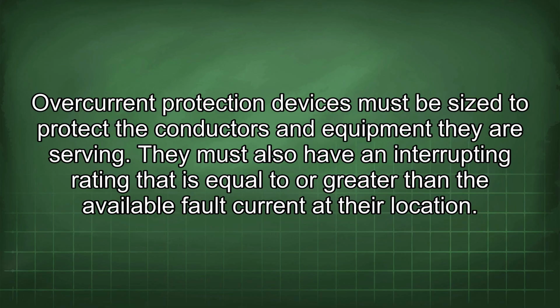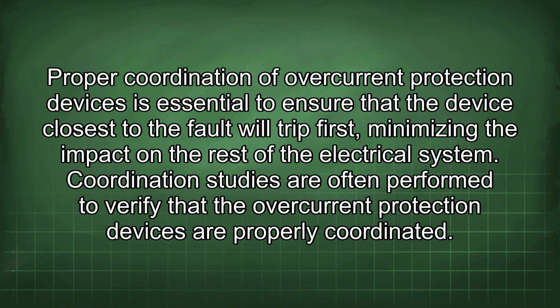Overcurrent protection devices must be sized to protect the conductors and equipment they are serving. They must also have an interrupting rating that is equal to or greater than the available fault current at their location. Proper coordination of overcurrent protection devices is essential to ensure that the device closest to the fault will trip first, minimizing the impact on the rest of the electrical system. Coordination studies are often performed to verify that the overcurrent protection devices are properly coordinated.